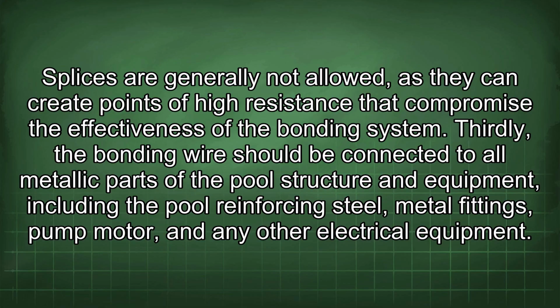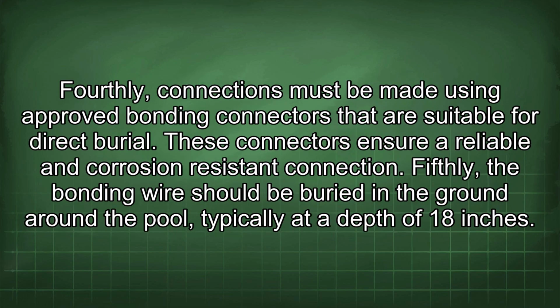Thirdly, the bonding wire should be connected to all metallic parts of the pool structure and equipment, including the pool reinforcing steel, metal fittings, pump motor, and any other electrical equipment. Fourthly, connections must be made using approved bonding connectors that are suitable for direct burial. These connectors ensure a reliable and corrosion-resistant connection. Fifthly, the bonding wire should be buried in the ground around the pool, typically at a depth of 18 inches.